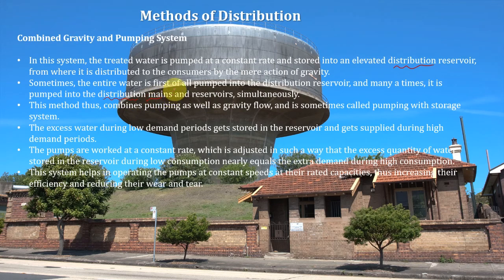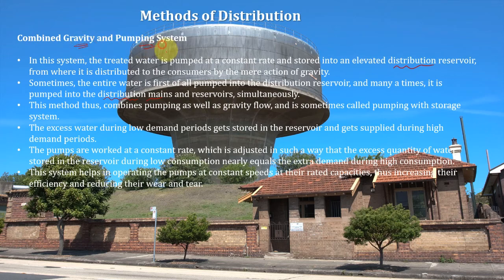Distribution mains are the pipes which carry water to people. In this method, you pump water into the distribution reservoir as well as into the mains. After water is pumped into the distribution reservoir, it then goes to the public by gravity. So in this system you are using both pumping and gravity — this is one of the most widely used methods. If a city is located at foothills, the best system would be the gravity system.